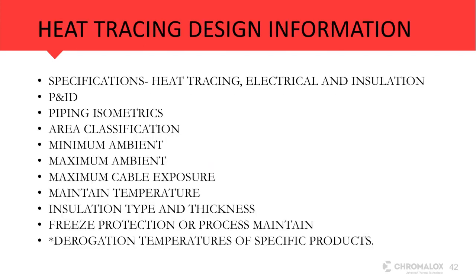One of the things we get asked a lot about is, what do I need to provide if I need to do a heat tracing design? Some of you may or may not be familiar with this, but this is the typical things we're looking for. We want the specifications of the heat trace, the electrical, and the insulation. So I covered those as the categories, as well as the P&IDs. The P&IDs are going to give me flow and non-flowing conditions, and that's how we're going to circuit something if we're going to do a maintain temperature, process maintain temperature application.